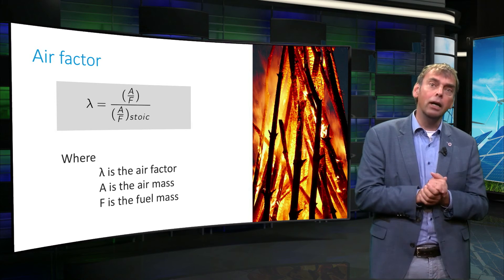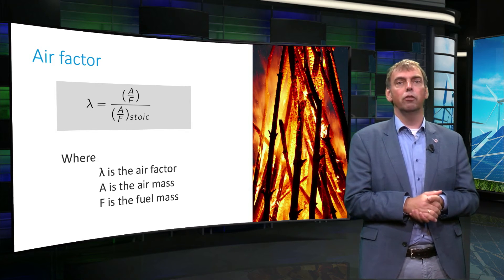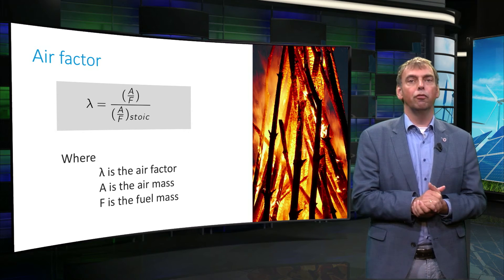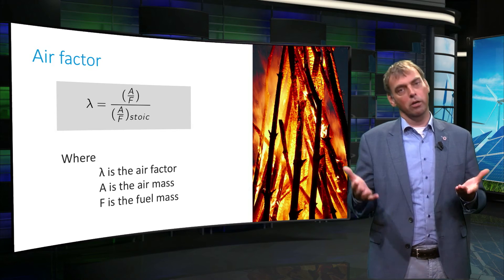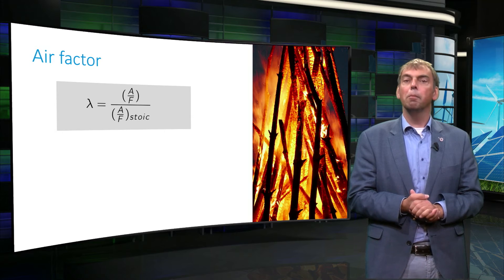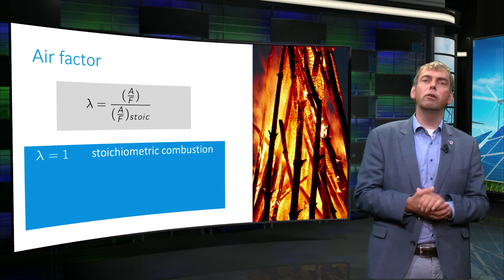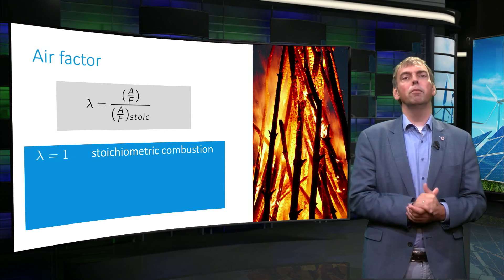The air factor lambda is the ratio of the mass flow of air to the mass flow of fuel divided by the same ratio, but then on the conditions of stoichiometric combustion. By definition, lambda equals 1 in stoichiometric combustion.